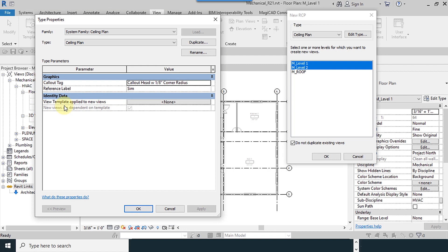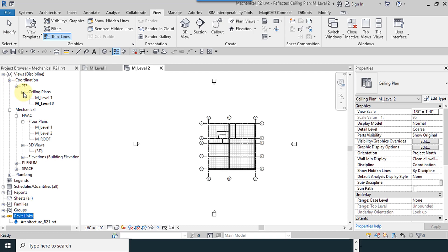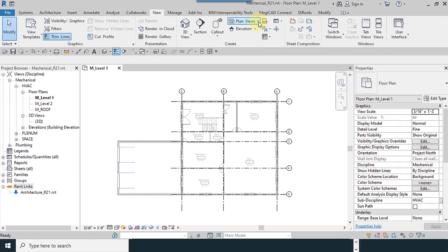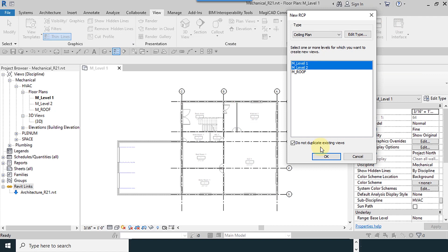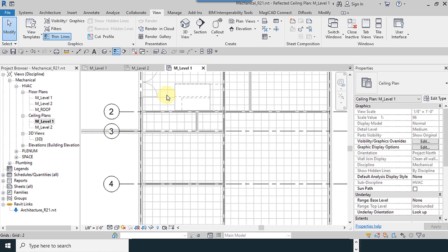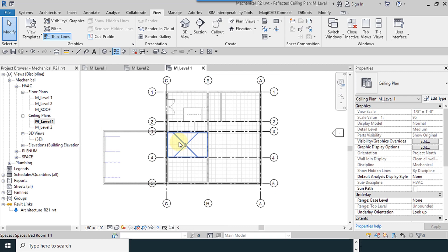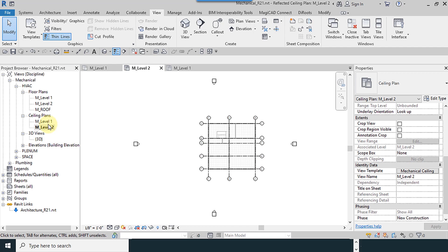So you can go to the view template. I do not want to do this now. Coordination has been added here. If I select the reflected ceiling plan, edit types, mechanical setting, okay, select level 1 and 2. So the coordination has not been added here. Okay, so the drop ceilings which the architect has added to the project are possible to see here, but their settings must be configured in the view template. These settings belong to the level 1 view template, the mechanical one, and it's also available for level 2.